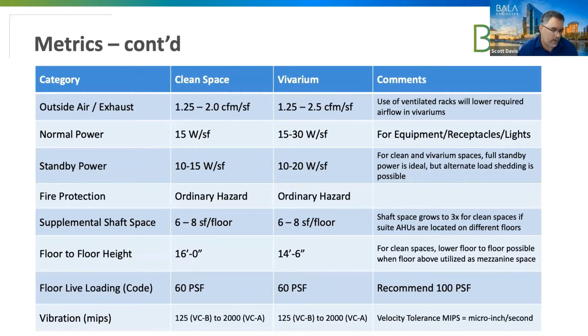Because as I note below, if we're keeping with the 1 to 2 CFM per square foot for outside air and moving that up and down the building, again, you're only needing 6 to 8 square feet per floor of shaft space. But if you're trying to move your clean space up and down, your clean room air, then that's going to increase at least 3 times that. So just something to be mindful of.